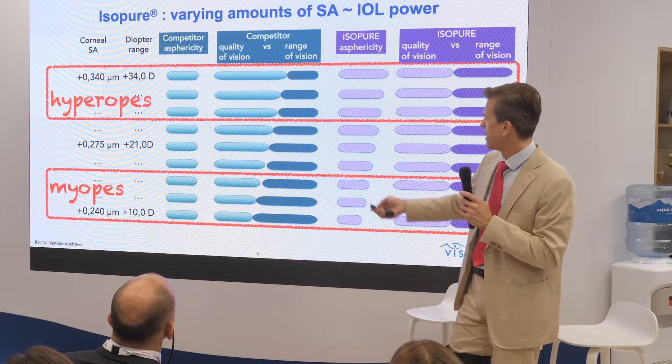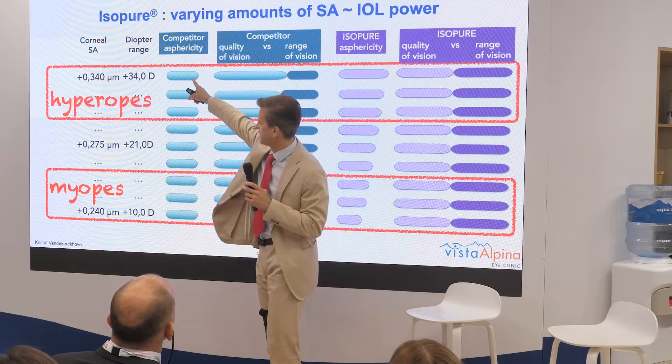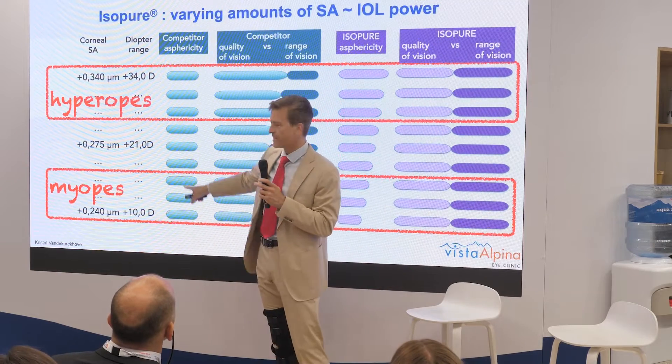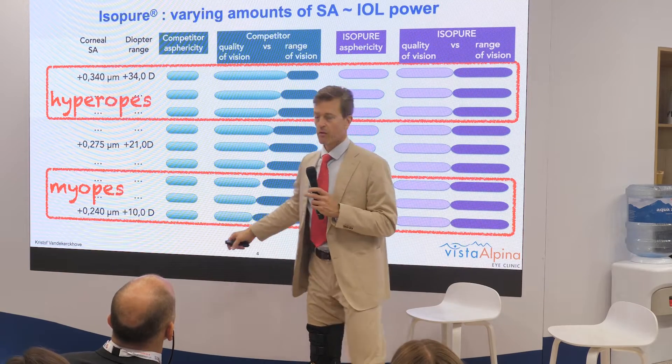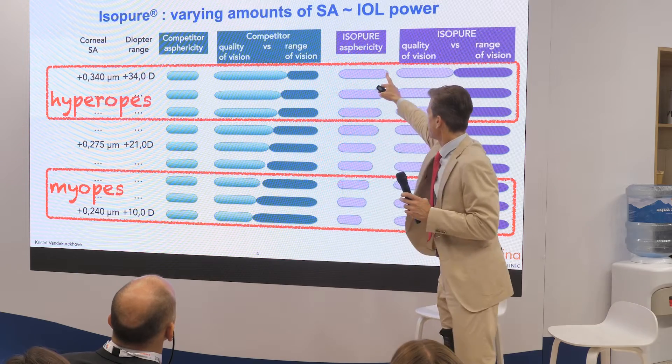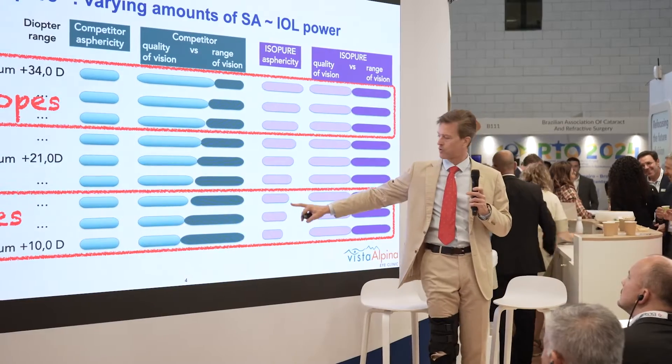This means the defocus is pupil-size independent. What I also like about this lens is that the defocus power — the asphericity — is customized according to the IOL power. For a competitor lens, the asphericity remains the same across the entire diopter range, whereas for isopure the asphericity changes.